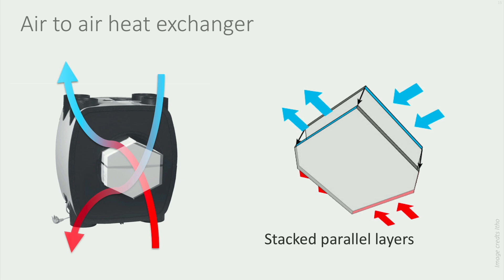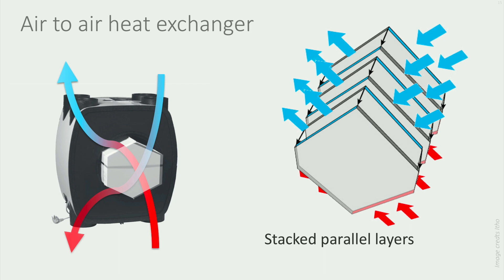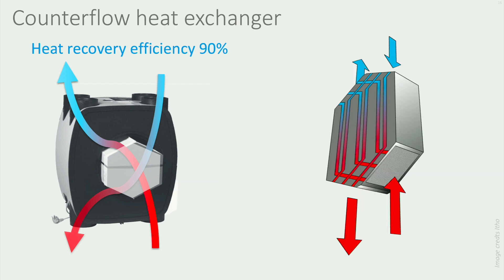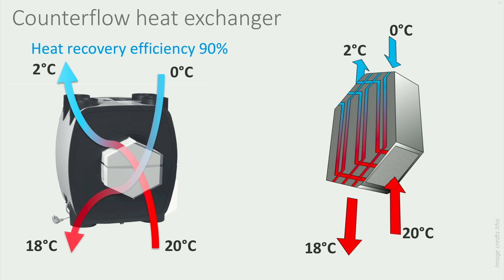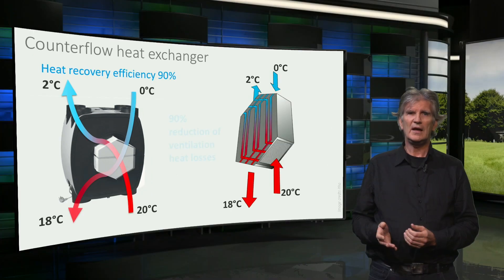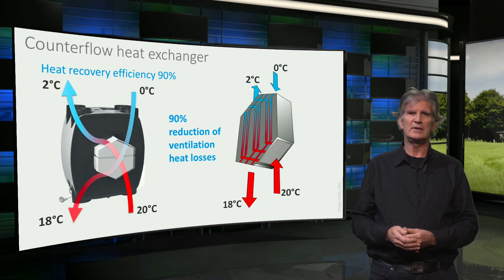The heat exchanger consists of parallel aluminum plates, creating dozens of small parallel air ducts, alternately for the incoming and outgoing air flow. The total heat exchange surface between the incoming and outgoing air flows is several square meters. This heat recovery unit with a counter flow heat exchanger has a heat exchange efficiency of more than 90 percent. So for example, when the outdoor temperature is 0 degrees and the indoor temperature 20 degrees, the heat exchanger will preheat the outdoor air to 18 degrees and the exhaust air will be cooled down to 2 degrees. As a result, the ventilation heat losses will also be decreased by 90 percent.